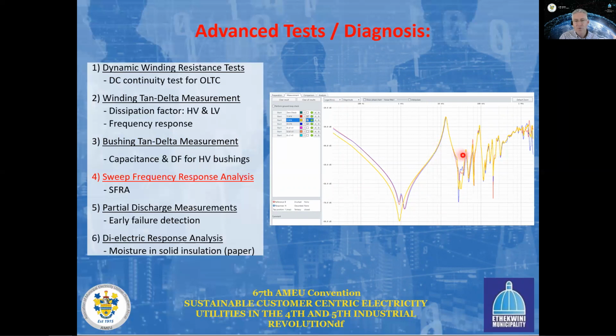It will give us an idea of the lower frequencies, where the core has changed, between 2 kilohertz and 20 kilohertz. If the bulk winding has somehow changed the geometrical configuration, 20 to 200 kilohertz gives us interwinding phenomena, and above 200 kilohertz up to 2 megahertz, we can see changes in the tap change leads as well as even the test leads as well. This is a comparative measurement.